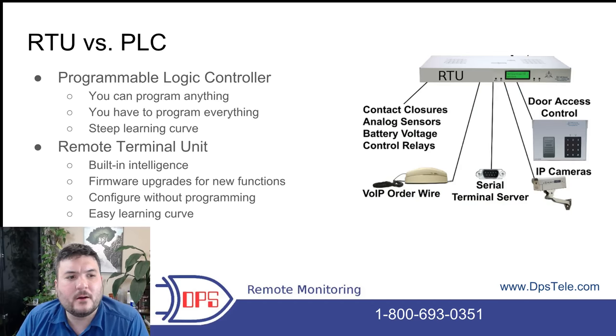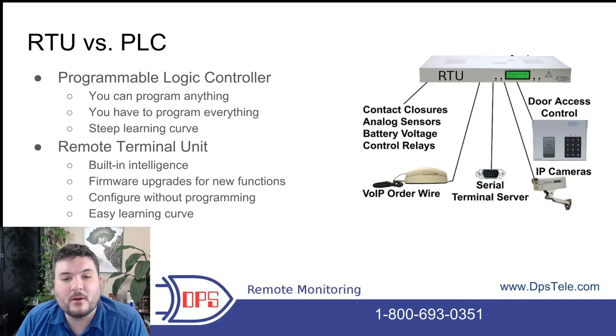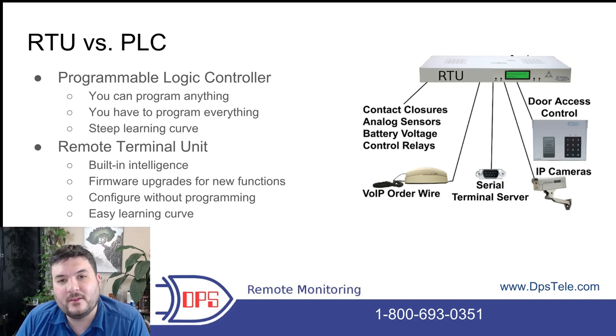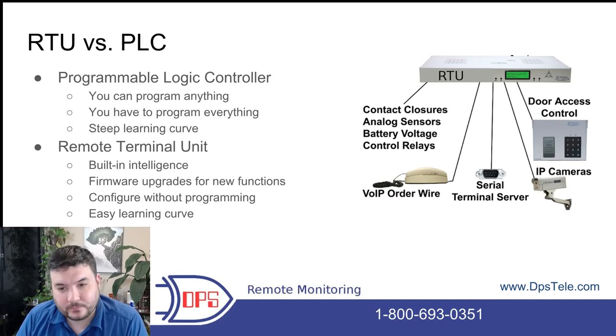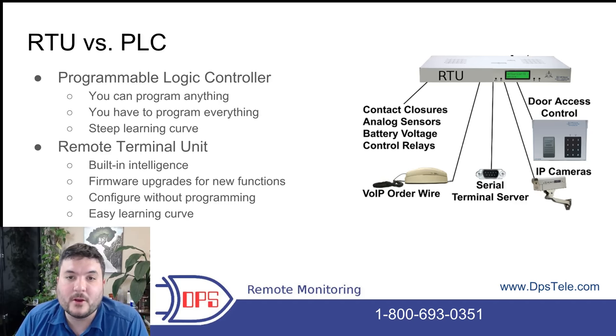One of the last things to cover is RTUs versus PLCs. A PLC is a programmable logic controller, very common in SCADA environments — if you're experienced, they can be powerful since you can program just about anything. But conversely, you have to program everything, so there is a steep learning curve. An RTU, or remote terminal unit, is different: it has built-in intelligence with a web interface where you configure it rather than program it from scratch. You type in descriptions for alarm conditions, set up if-this-then-that rules, and you're likely to get firmware upgrades for new functions from your manufacturer. RTUs definitely have an easier learning curve, and if you're just getting started, it's an option you should consider.